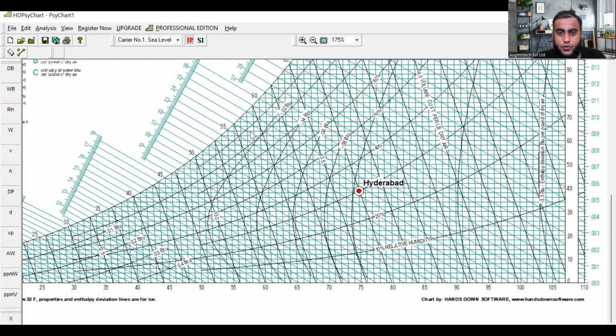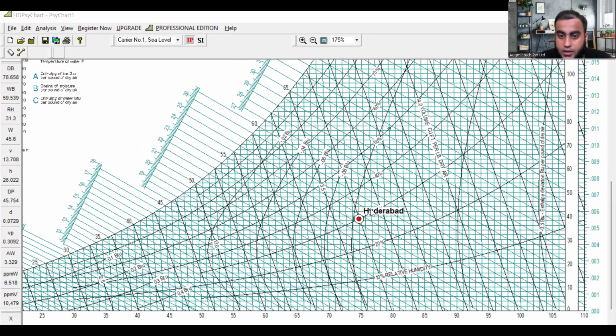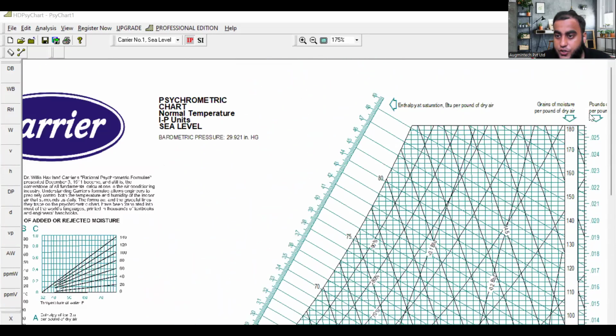Okay, our main target is not that. Our main target is that we know the dry bulb temperature and relative humidity. So you can see here we have got one point which is on the 30% line. See, 20%, 40%, between them this curved line is showing. This is the 30% curve. So here we have got one point, and the temperature which we are maintaining is 75. So we have got the point. Based on this point, when you take the cursor along the horizontal line, here you will get the value. See, this is your humidity ratio value, and the unit is also given here.